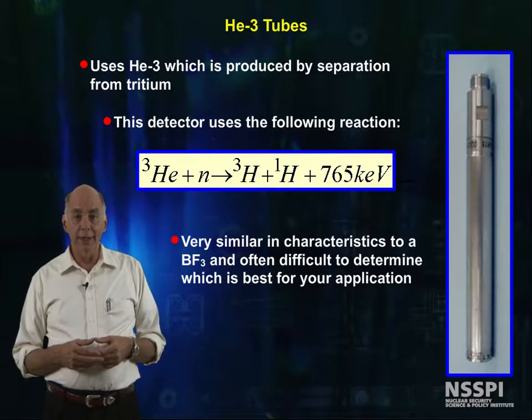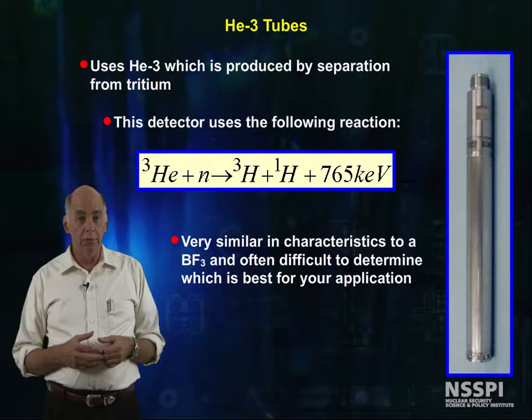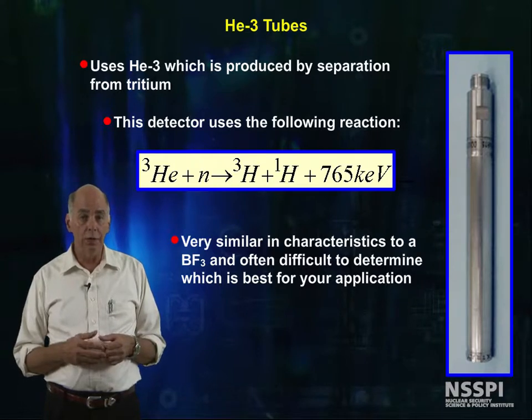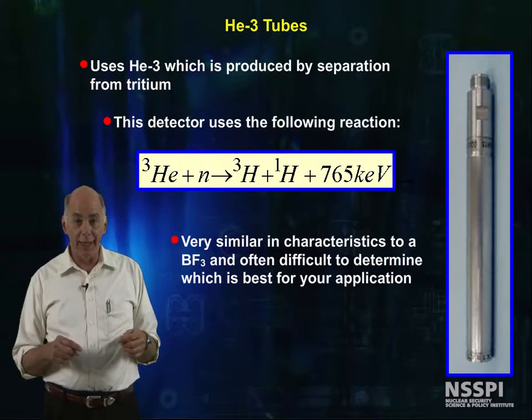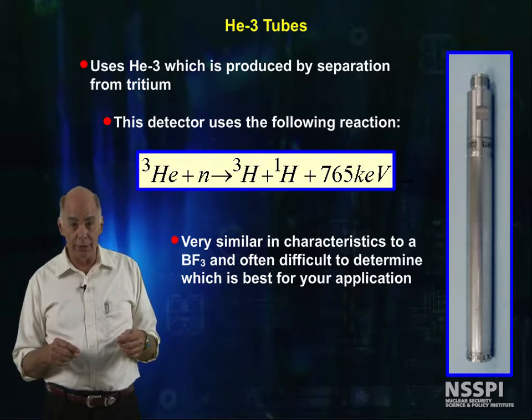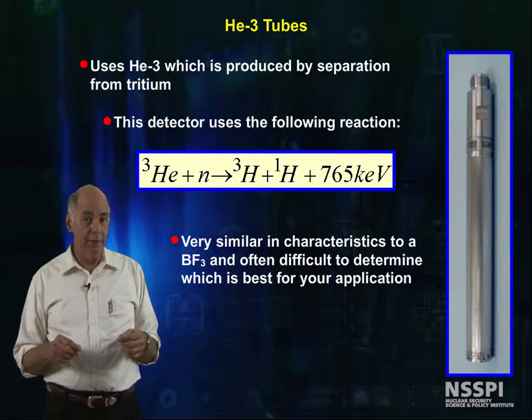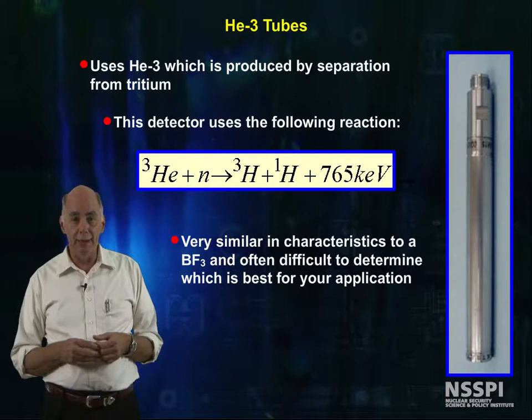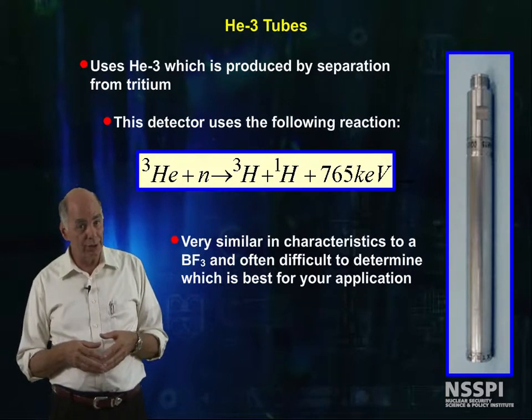Helium-3 detectors have very similar characteristics to a BF3 tube, but one difference is that the helium-3 itself works as a wonderful counting gas, so you don't have to add another gas to help with the counting characteristics. But they are generally more expensive than BF3 counters. Sometimes extra gases are added to more quickly stop the reaction products, but that's a different story.